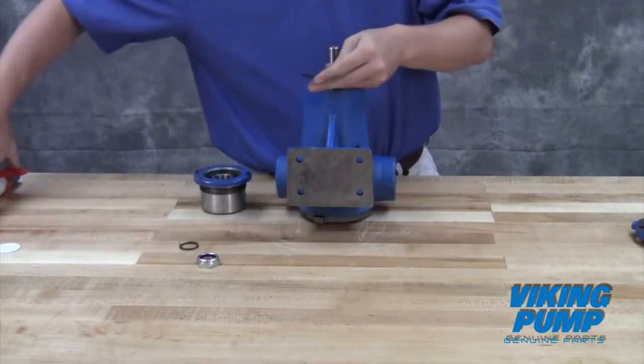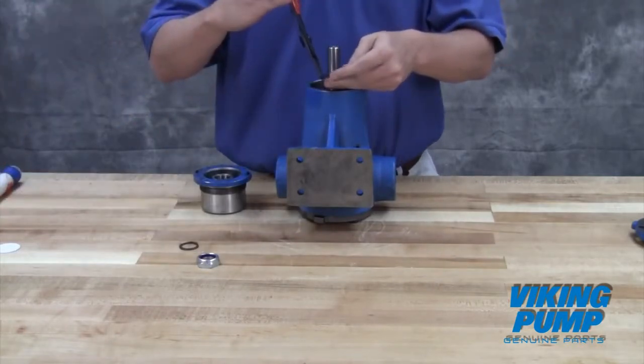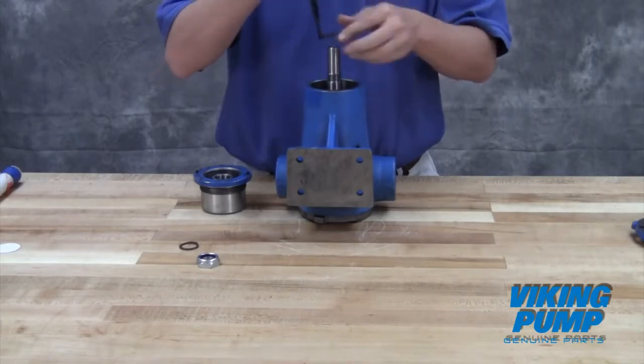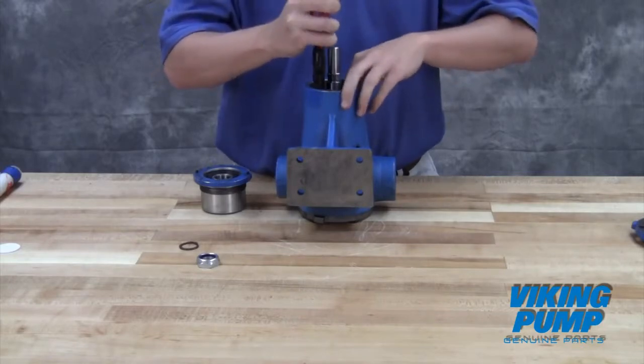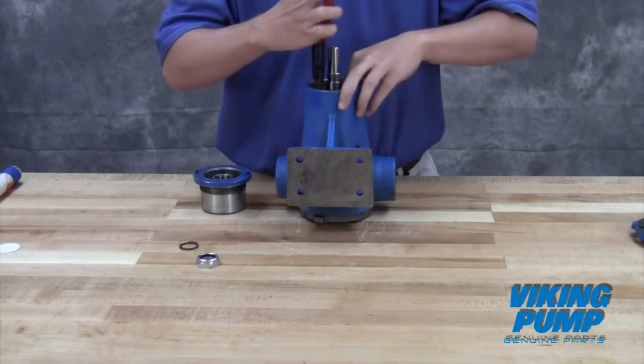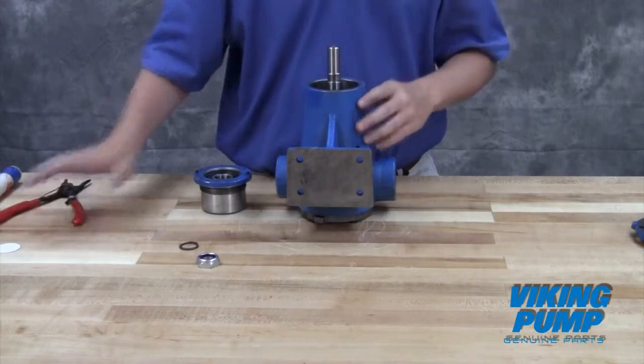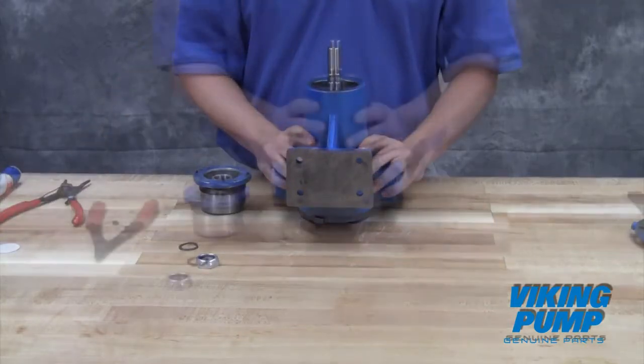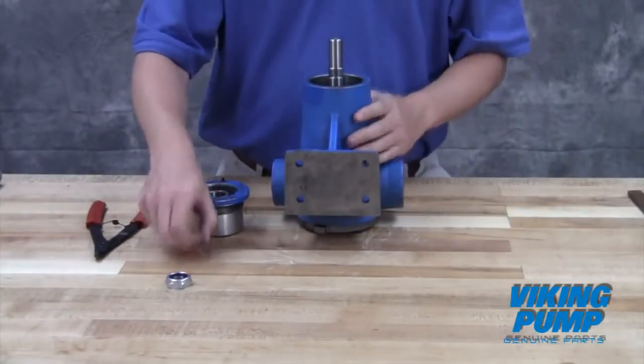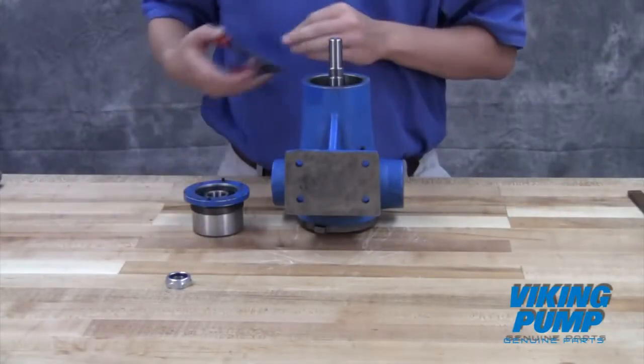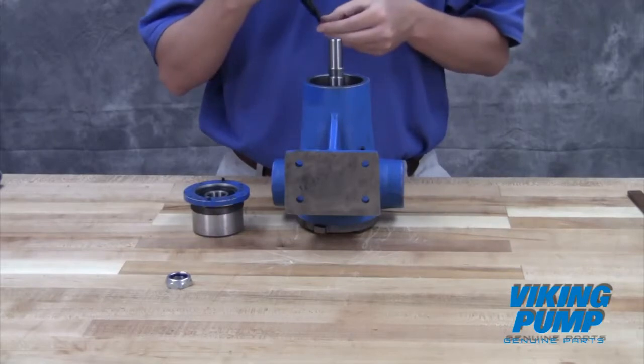Install the bearing retaining ring. Be sure to include the bearing retainer washer first on AS, AK, and AL models. No retaining ring is used on these models, but a bearing spacer collar will be installed next. Once all required retaining rings and spacers are installed, reinstall the outer bearing housing.